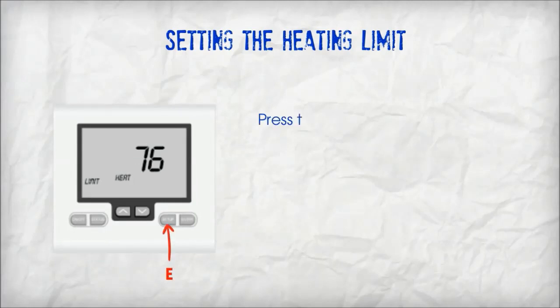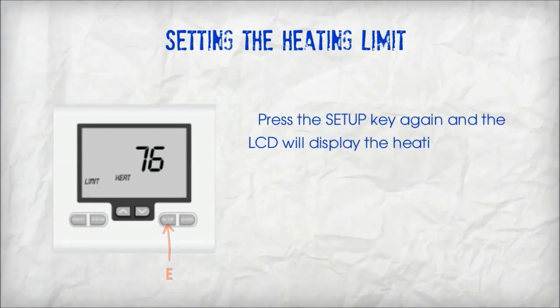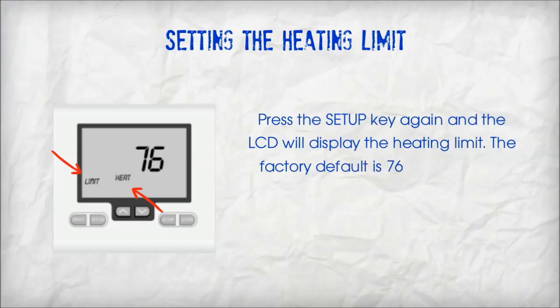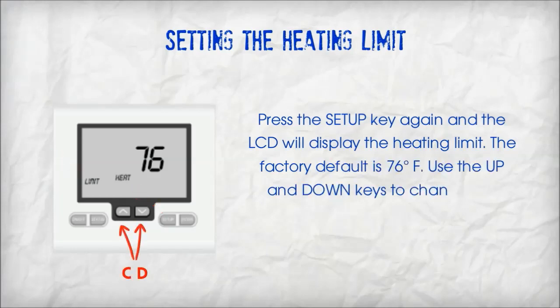Setting the heating limit. Press the setup key again and the LCD will display the heating limit. The factory default is 76 degrees Fahrenheit. Use the up and down keys to change the heating limit setting. If using a zone panel, it's recommended not to go above the factory default.